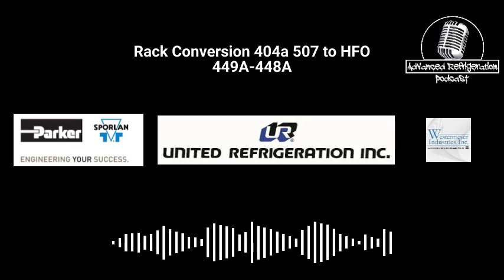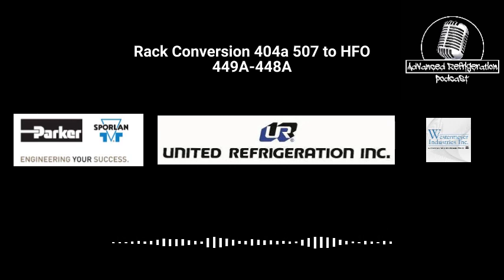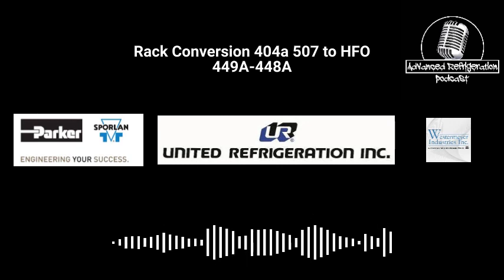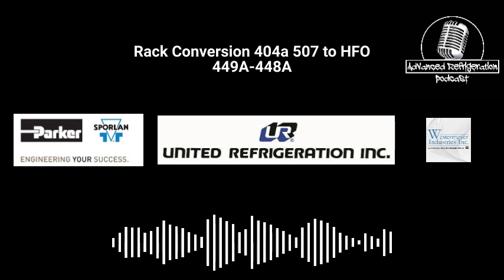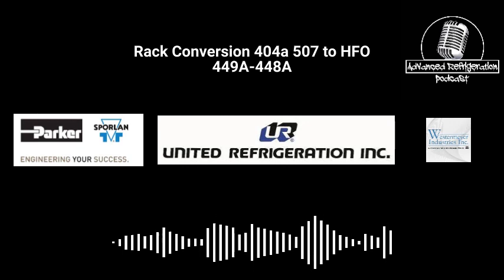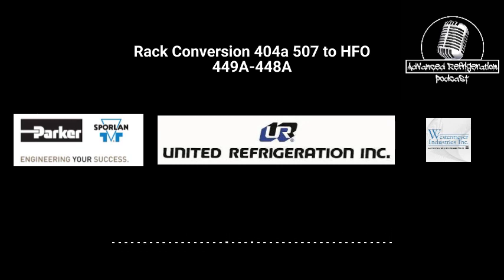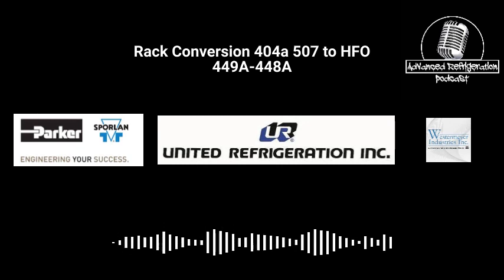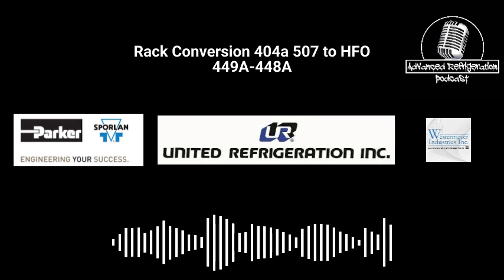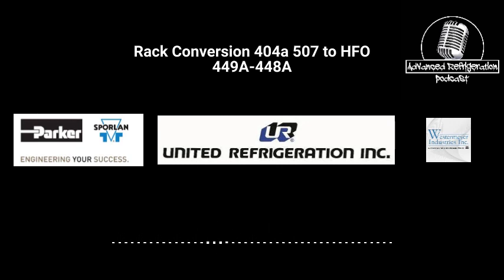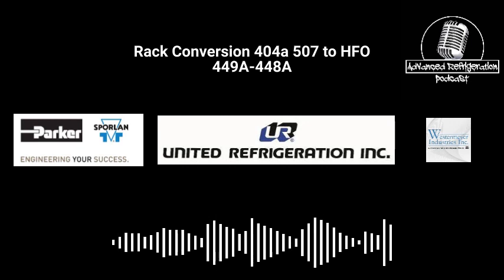That's part of these retrofits, like adding digital compressors in. I always sell that as an upcharge, trying to get the customer to do it because you're going to have capacity issues otherwise. So why not do it when it's cheap. That's the thing I like about the Bitzers, they'll let you unload both heads. On a Copeland you can't do that because of the way the oil's set up from the oil pump passages. That's one advantage you get with the Bitzer, you can unload both heads. Variable speed is obviously king now, but the digital unloading, that CME module is way better than the Bitzer's old digital unloading, which was super laggy.